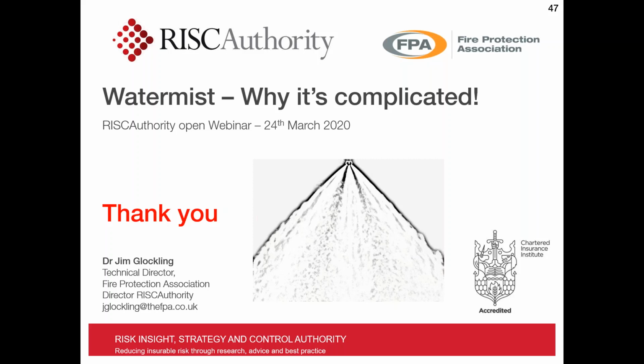But again, that is a nice case where the ability of the system to perform has dependencies on many other things. Interlocks with the gas supply, the ventilation, or the electrical supply to the heating equipment. The ability to perform in that environment is also inherently linked with the duct cleaning regimes and how well that is done, and that is all compliant also. So it's a complex area with a lot of additional requirements.